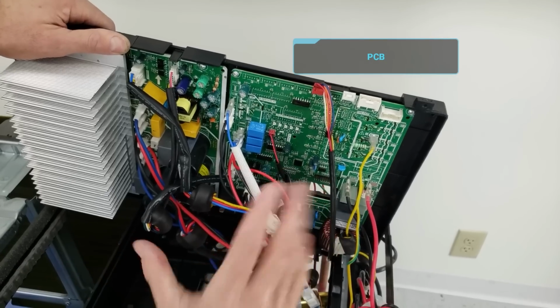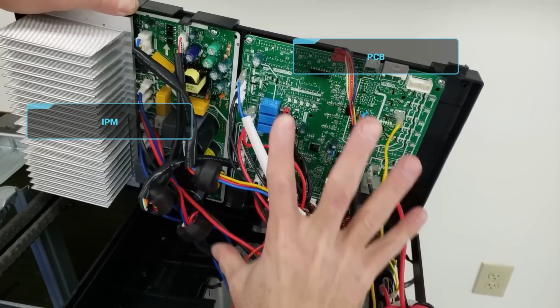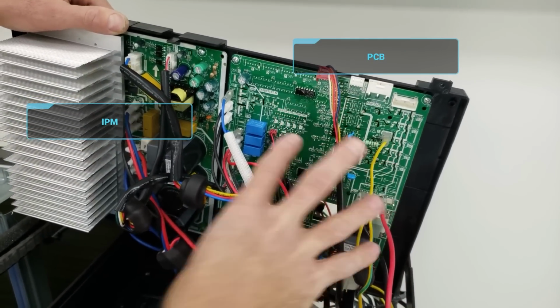But in reference to the other things, you could also have voltage spikes or lightning or something that has damaged the main PCB in the outdoor unit or the IPM, the intelligent power module. And so you want to have a surge protector on the outdoor unit, and you could also potentially install some type of a voltage monitoring system with surge protection to temporarily short that to the ground if you have a lightning strike. That's a big thing, is these circuit boards are very sensitive.